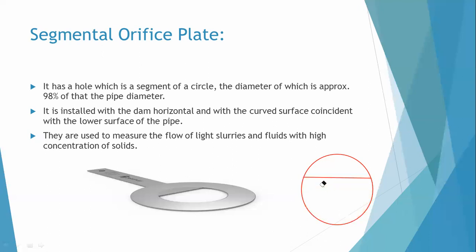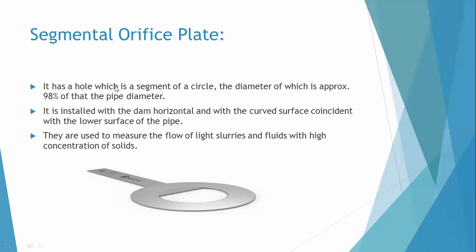The segmental orifice plate has a hole which is a segment of the circle. If you draw a line across a circle, the portion cut off is called a segment of the circle. The hole in a segmental orifice plate is shaped as a segment of a circle, the diameter of which is approximately 98% of the pipe diameter.